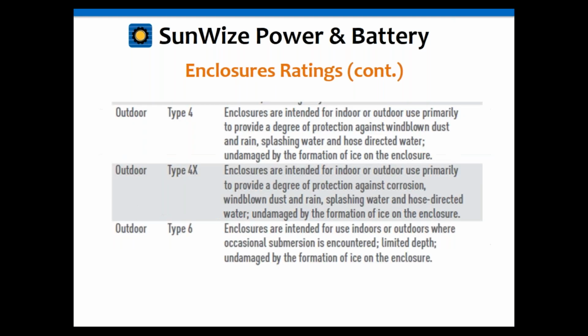You'll see the same thing with the NEMA 4. The difference between NEMA 4 and NEMA 4X is just that X has that corrosion resistance. That could be the difference between a painted steel and a powder-coated aluminum or stainless steel box. The powder-coated aluminum and stainless steel would be considered 4X, but painted steel would only be considered 4. Both of them are sealed boxes—I want to highlight that. They're sealed to prevent water from getting in from any direction, so you can spray a hose at it from all angles and the water will not get in.